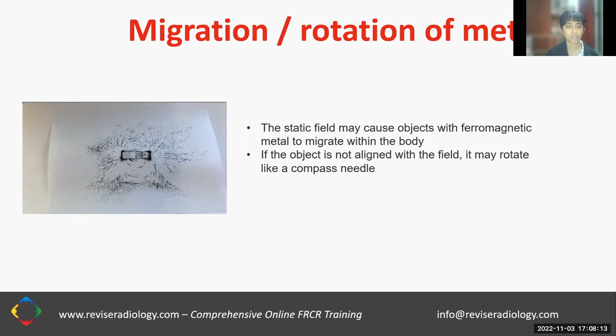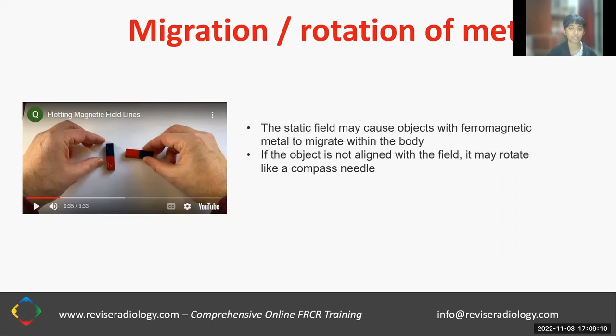A similar thing happens when there are objects with ferromagnetic material within the patient's body when they're subject to the magnetic field. The static field may cause these objects to migrate within the body, that is to move along the magnetic field lines. And if the object is not aligned with the field, it may rotate like a compass needle within the patient's body in order to get aligned with the field. So this is another of the effects that can happen. This is due to metal with ferromagnetic areas or domains in them when they're within the patient's body itself. So the ferromagnetic missile effect happens with objects outside the patient's body, and the migration or rotation of metal occurs with metallic objects inside the patient's body.